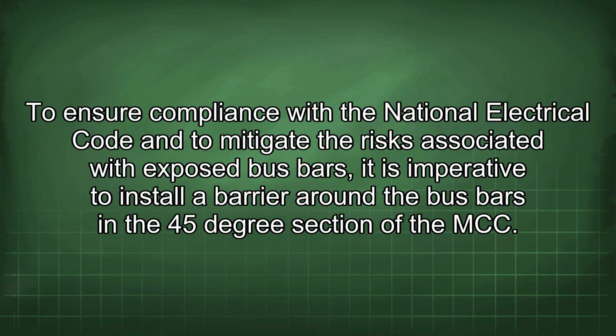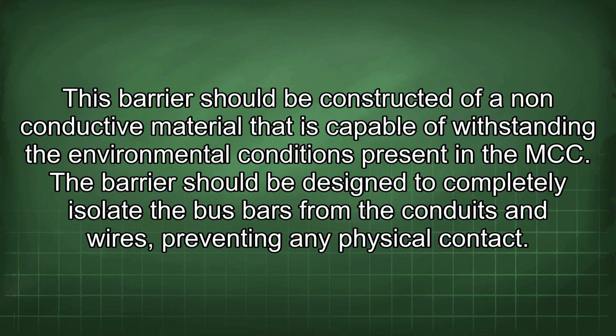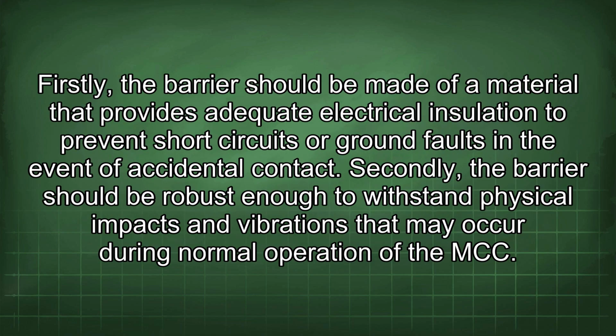To ensure compliance with the National Electrical Code and to mitigate the risks associated with exposed bus bars, it is imperative to install a barrier around the bus bars in the 45-degree section of the MCC. This barrier should be constructed of a non-conductive material that is capable of withstanding the environmental conditions present in the MCC. The barrier should be designed to completely isolate the bus bars from the conduits and wires, preventing any physical contact. Firstly, the barrier should be made of a material that provides adequate electrical insulation to prevent short circuits or ground faults in the event of accidental contact.